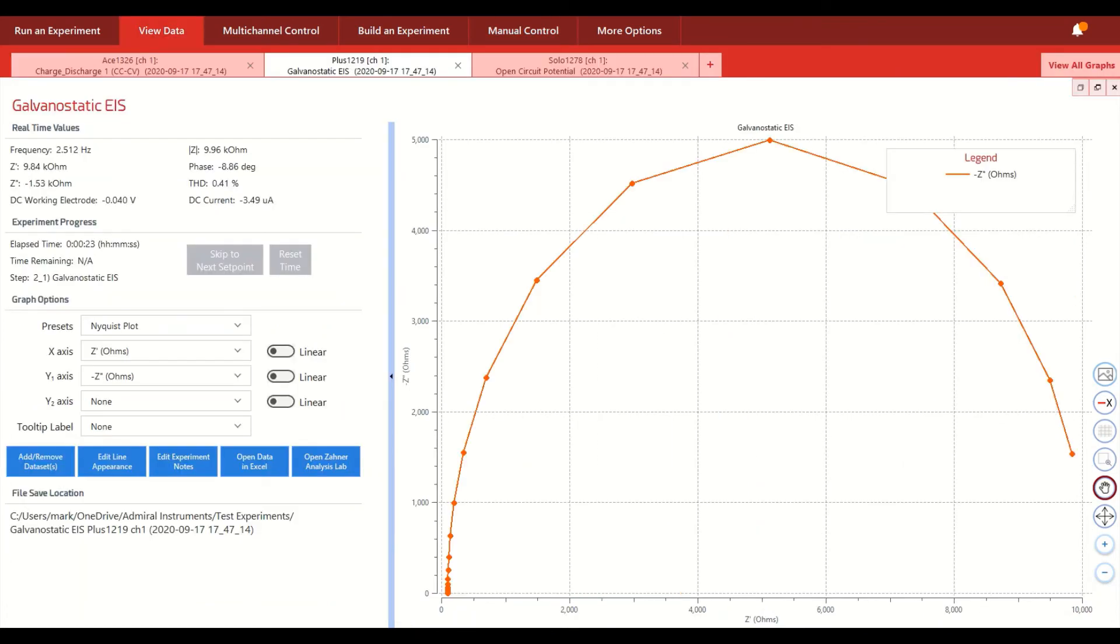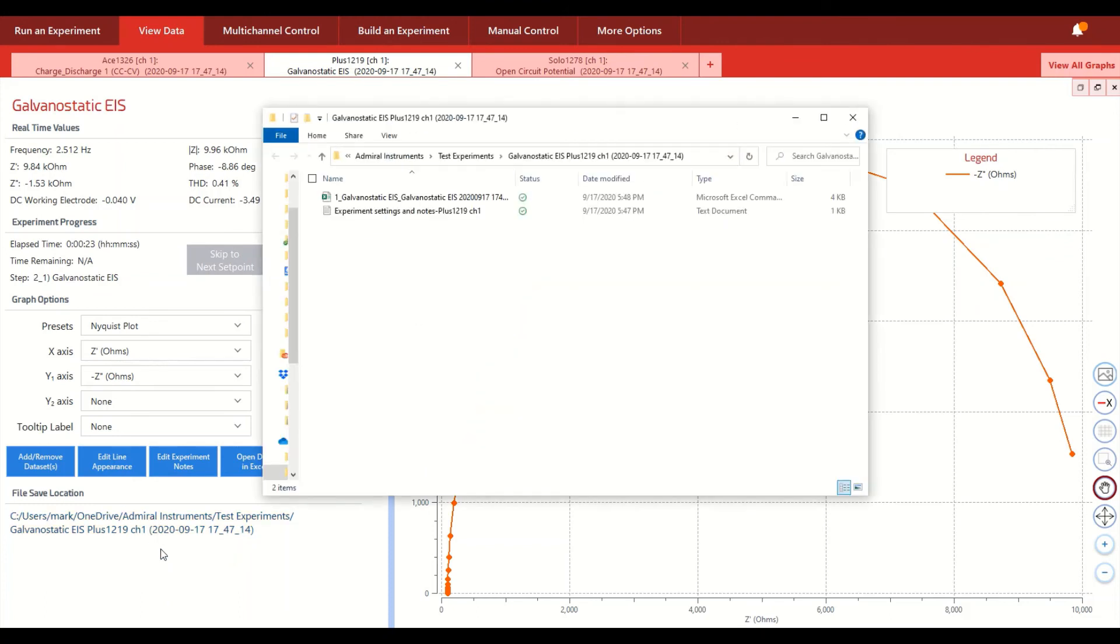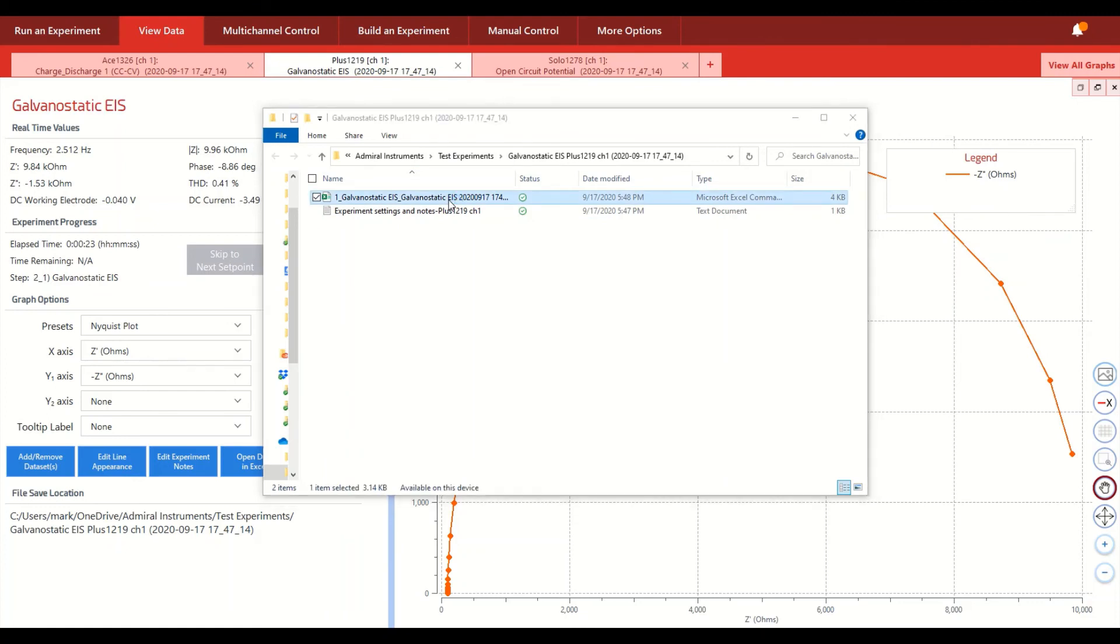Now, one of the biggest issues that many electrochemists face when operating their potentiostats, particularly older brands of potentiostat, is to very seamlessly be able to take their raw data that they collect from their instrument and get it in their hands so that they can analyze it and do whatever else needs to be done to it. But the point is getting the raw numbers is oftentimes a time consuming challenge. With our software, we make it very easy to access the file save location that was picked when the experiment was first being configured. And now that we've opened up the file save location, all of the data is stored natively in a CSV file format.